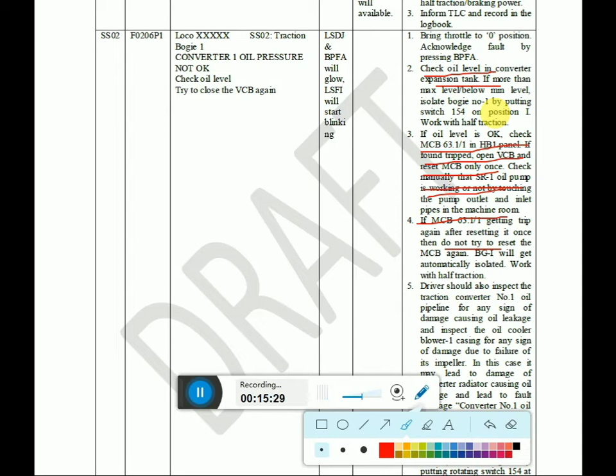After that, we have to check MCB 63.1/1 for SK1, traction converter pump 1, and 63.1/2 for SK2, traction converter pump 2. If any MCB trips, we can reset. If oil is below the minimum mark, we can isolate traction converter 1. Similarly, if any of the OCB, TMB, traction converter pump 1 or pump 2 MCB trips, after resetting they trip again, we should not reset, isolate the concerned traction converter and work with the other traction converter with 50% of maximum load.